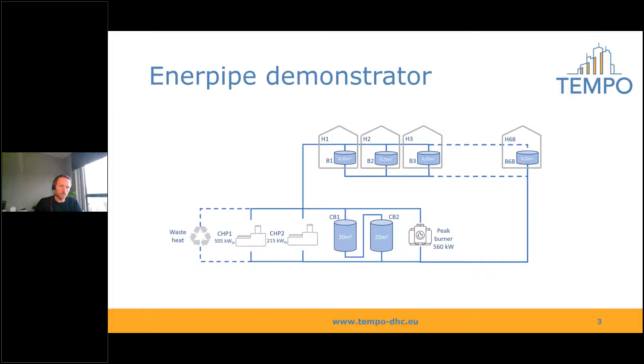So here you can see a very simplified version of the network in Windsbach. The most important thing to note here is that the heat production can come from several different producers. You see there are 2 CHPs, but there's also a peak burner. Then we also have some heat coming in from a waste heat plant. And there are 2 large central buffers of 40,000 liter, so 20,000 liter each. Connected to them are the buildings with the decentralized buffers. Most of them are the 250 liter buffers, but there are also some buffers that are 600 or even 1000 liter.